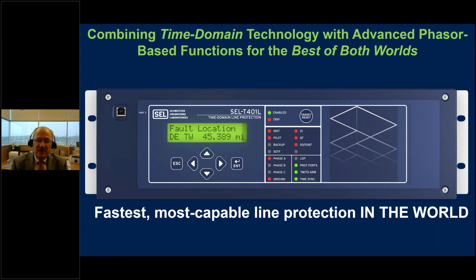That's transmission. I want to talk also about speeding up the game on distribution. Here we have a portion of a distribution system, and here's a recloser protecting a feeder, and there's a couple of branches here that are protected by fuses. And we've got an age-old problem here when traditional protection is used, where you try to coordinate these fuses with the relays. If you have a fault on, say, this fuse lateral, the relay doesn't know where it is, so the time coordination principle is to wait to see if that fuse is going to blow.